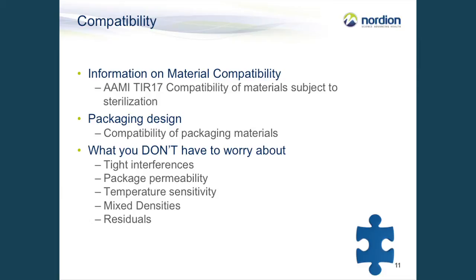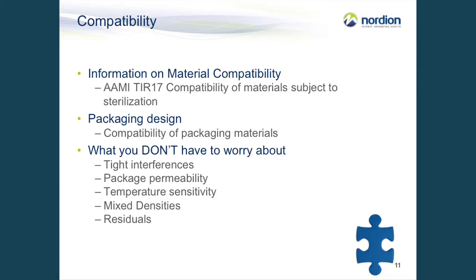With gamma, some of the things that you don't have to worry about when it comes to compatibility include tight interferences, such as the junction that happens between metal and plastic pieces in some orthopedic devices, which can cause issues if you're using a gas-based sterilization technique, which has to get between that interface. Package permeability might be a requirement for gas or moist heat processes. Temperature sensitivity: while there is a temperature increase with gamma processing, usually maximum values are around 40 degrees Celsius, and even these moderate temperatures can be compensated for by pre-cooling or actively cooling devices during irradiation.